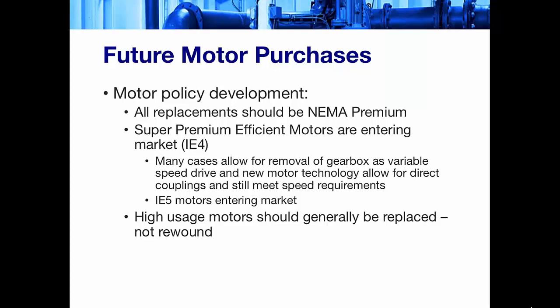One thing you might want to consider is that for motors that are in service a lot of hours a day, you replace them with NEMA Premium and don't rewind them. However, the motor rewind shops are getting in on the game of guaranteeing efficiency and showing you test results on the rewind. So, in the spirit of recycling and utilizing existing resources, we can take it to a motor shop that can guarantee us basically NEMA Premium motor efficiency on a rewind. So do your homework when you're looking at rewinding your motors.